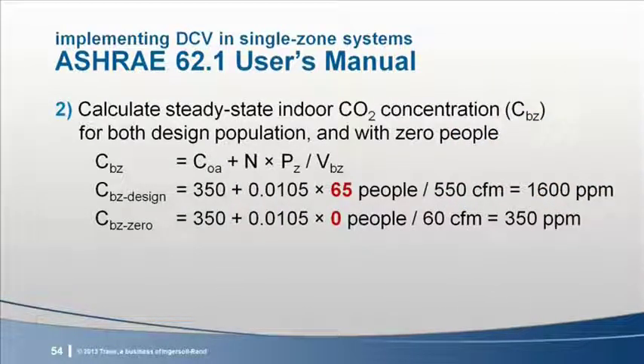The second step is to calculate the CO2 concentrations using the steady state equation found in the standard. For our example, assuming an outdoor concentration of 350 parts per million, the indoor concentration of CO2 that corresponds to peak population is 1,600 parts per million. And the concentration at zero population is 350. These values define the endpoints for a simple proportional control sequence.